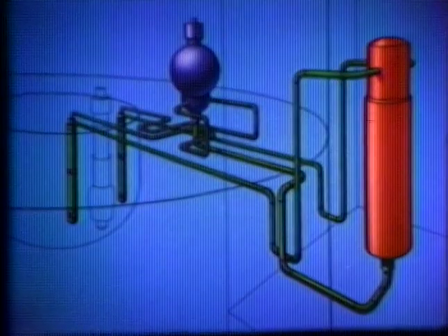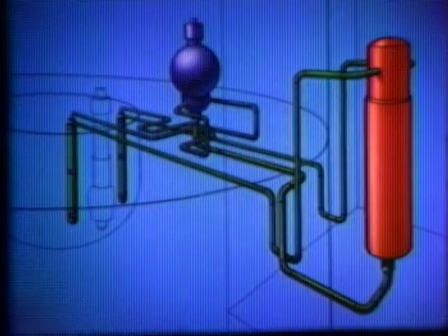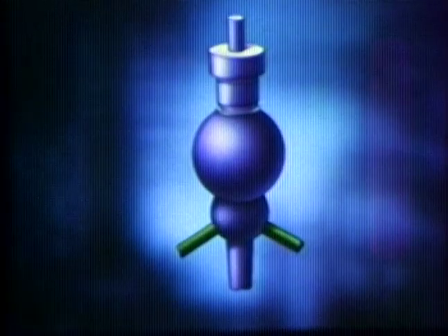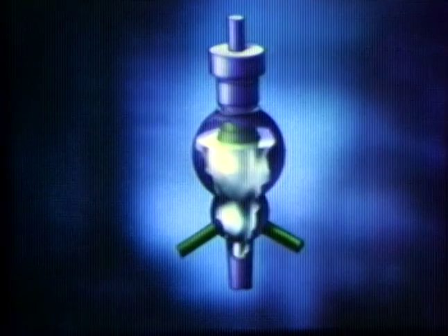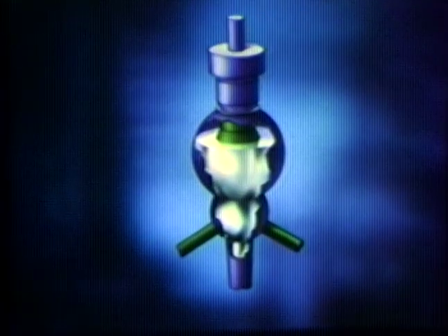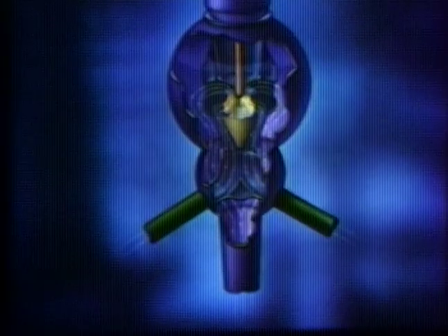The 400 tons of this non-radioactive sodium contained in each secondary loop are circulated by a secondary pump built into a 5-meter diameter expansion tank. Rotation of the pump provides a flow of over 3 tons per second.